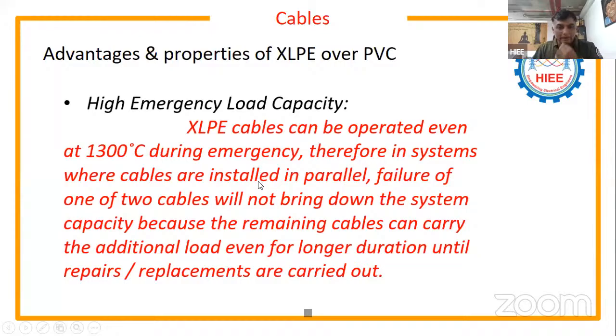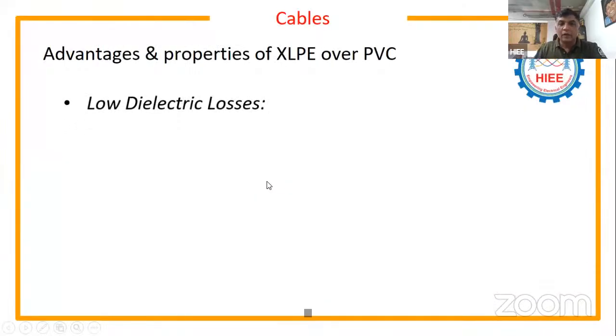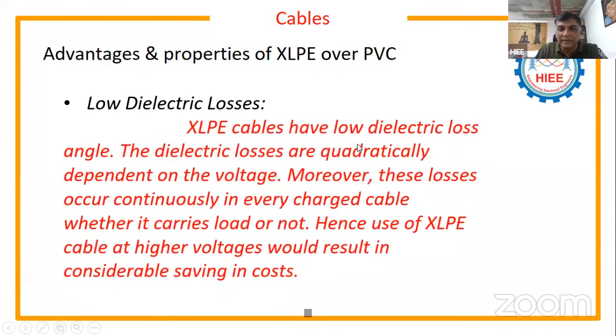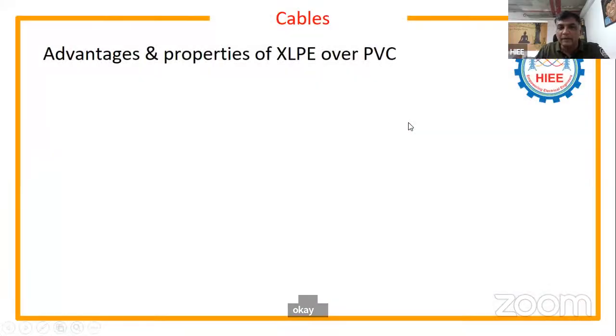Okay, and low dielectric losses. XLPE cables have a low dielectric loss angle. The dielectric losses are quadratically dependent on the voltage. Moreover, these losses occur continuously in every charged cable, whether it carries load or not. Going with XLPE cable at higher voltage would result in considerable savings in cost.